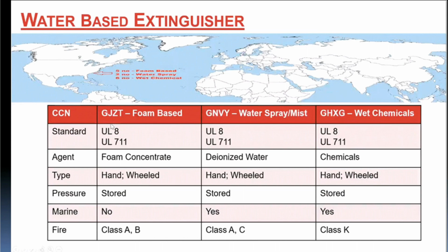So I would like to finish this discussion with a question to you. What you see here are different types of water-based extinguishers. For example, consider this wet chemical class K extinguisher. For this extinguisher, the UL listed manufacturer, we can see only in the USA. Other than the USA, I saw one more approved UL listed manufacturer in Greece. Other than these two, I couldn't find any approved manufacturer throughout the world, even Asia, Middle East, nothing. When it comes to fire pumps, we can see many different manufacturers in the Middle East, even China. But when it comes to water-based extinguishers, what is the problem in getting the approval? We can find them only in the US. Other than this, nothing is there. So this is the question. When you can get the approval for a fire pump, why can't you get the approval for the water-based extinguisher? This is a very simple item. Is there any special requirement to give the approval for this one?